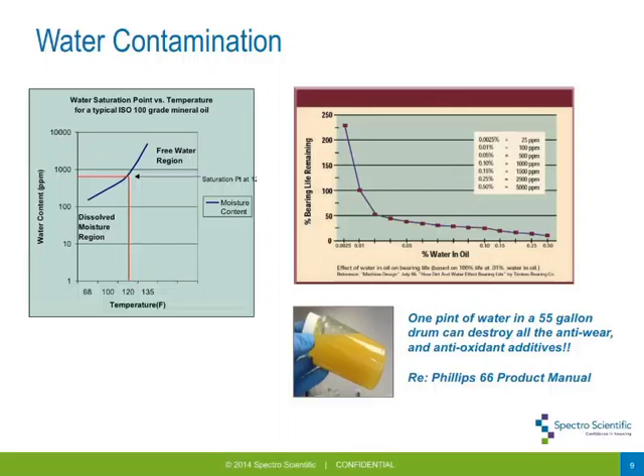Another common problem is water contamination. Water is a particular challenge because it can coexist in oil. Oil is hygroscopic, which means that if you leave an open bottle of oil out to the atmosphere, moisture will be absorbed into the oil due to weak electrostatic attraction, up to its saturation level. Above that point, if water is still present in the environment, it will come out as free water. We want to keep oil as dry as possible, because water in oil will cause premature wear, loss of viscosity, loss of load-carrying capability, and excessive heat.